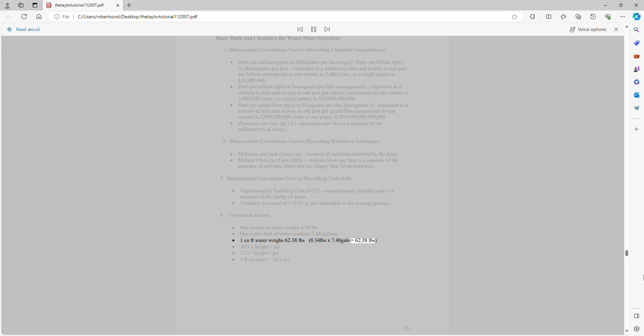Conversion factors: 1 gallon of water weighs 8.34 pounds. 1 cubic foot of water contains 7.48 gallons. 1 cubic foot of water weighs 62.38 pounds (8.34 × 7.48 = 62.38). 0.433 × height = psi; 2.31 x psi = height. 1 foot of water equals 0.433 psi.